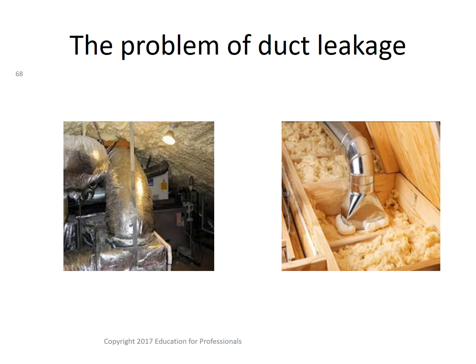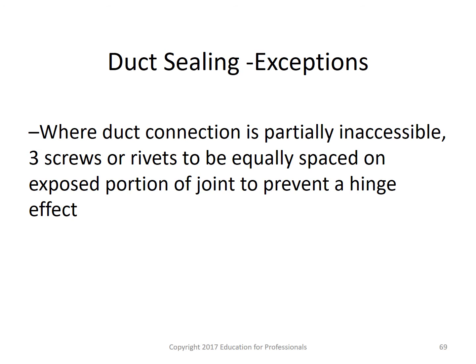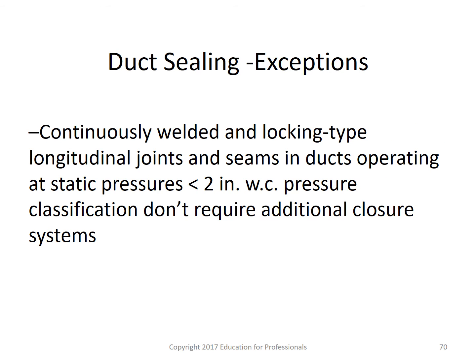To ensure ducts are tight, have your HVAC contractor conduct a duct leakage test, so you can at least know where you stand, and this is an imperative. At least have a good idea of how well the ducts are working or how well they are not working. And here are some of the duct sealing exceptions. We'll also take a look on the next slide at a few more. Again, the duct sealing exceptions.